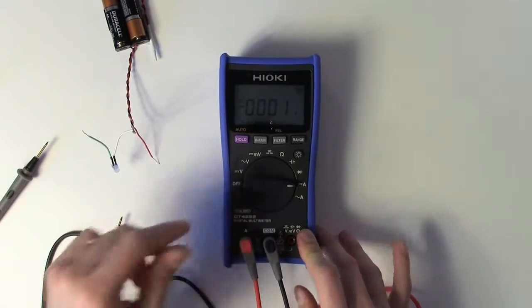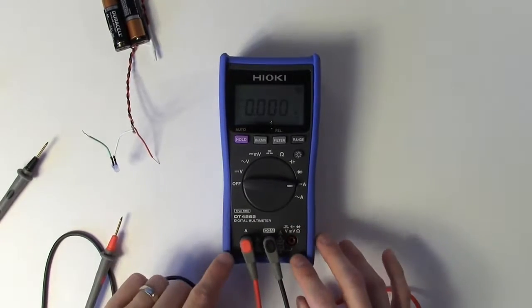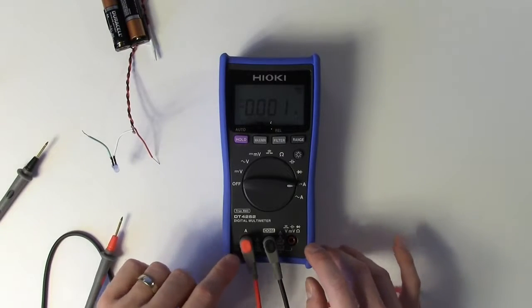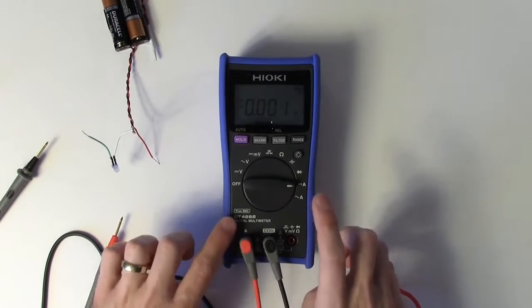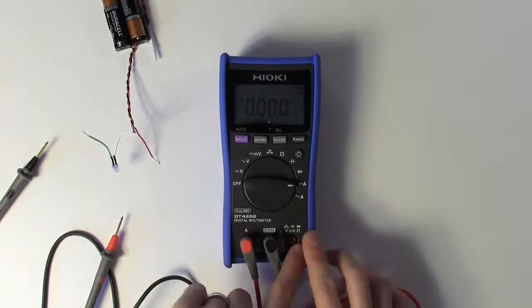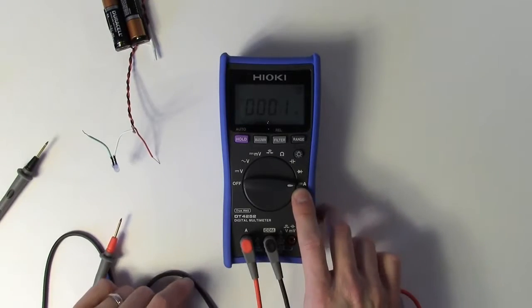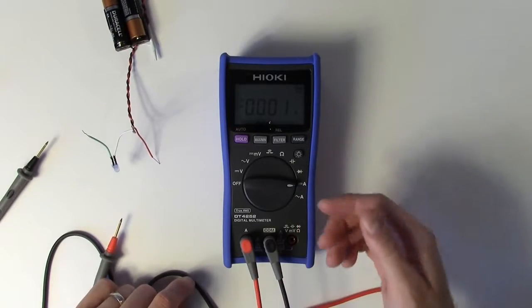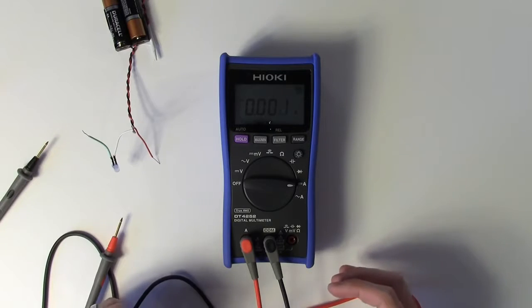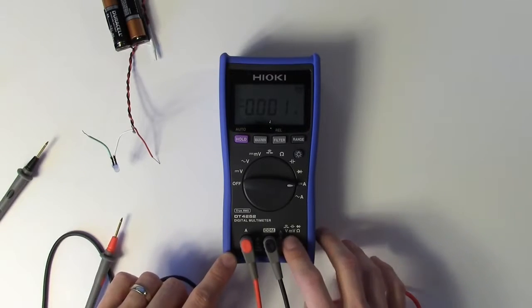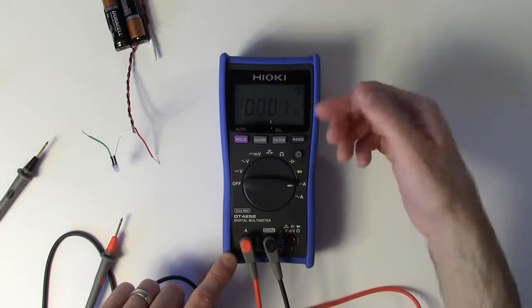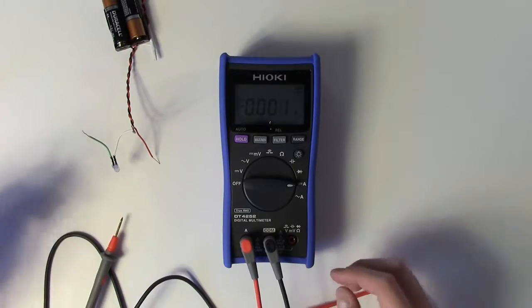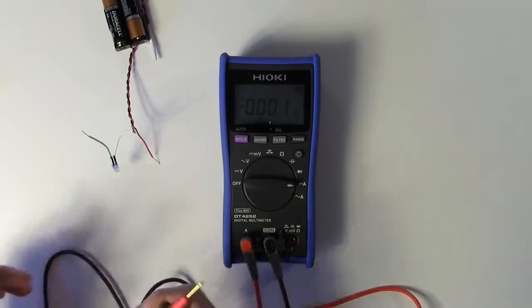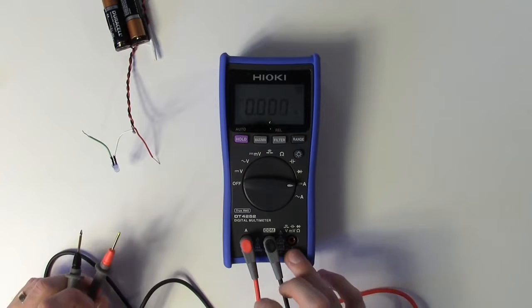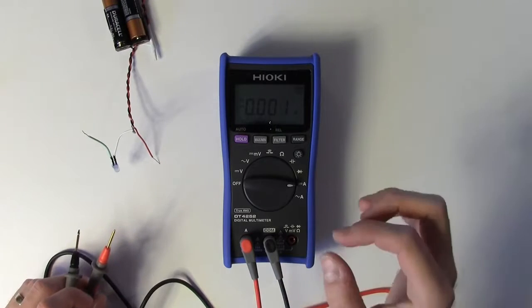Another minor drawback of this meter is that it doesn't have any sort of terminal monitoring or protection. So it is possible to have the probe in the wrong terminal and on an inappropriate setting, and it won't be able to really tell you in advance. There are no shutters, there's no optics within the terminals to alert you as to whether you have them in the right positions.